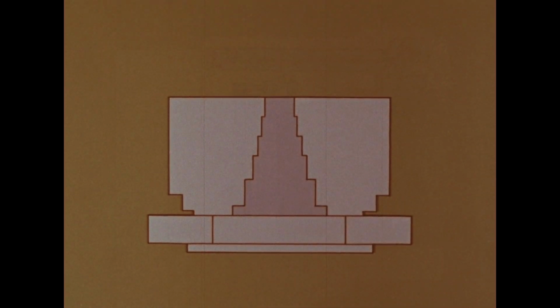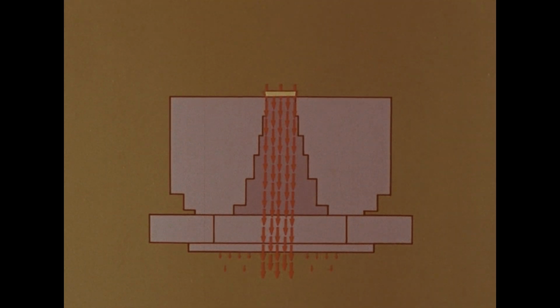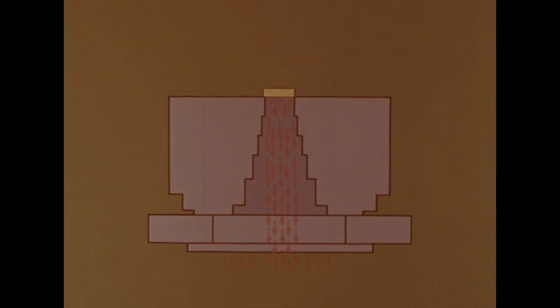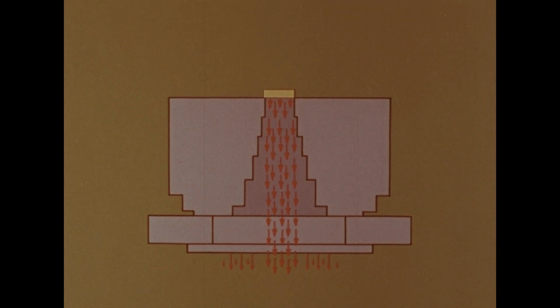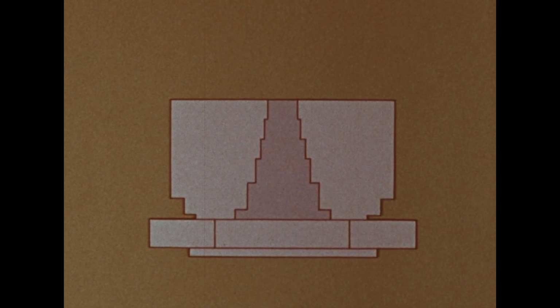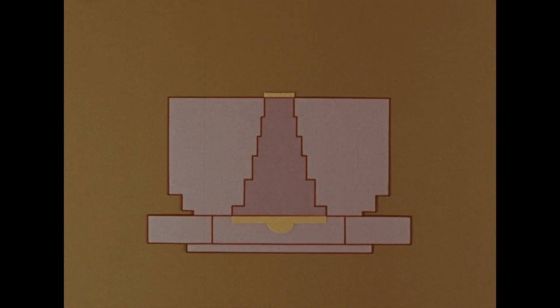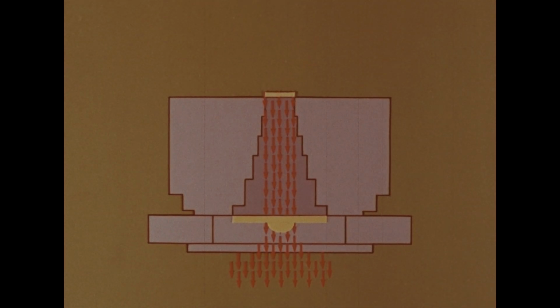Now, instead of having a target, the beam path is allowed to hit a very thin scattering foil. A very thin foil will scatter the electron beam in the form of a Gaussian distribution. A very thick foil will widen the curve but produce photon radiation and decrease the beam energy. The Siemens Mevatron uses a two-foil system for ideal dispersion of electrons with almost no photon production.